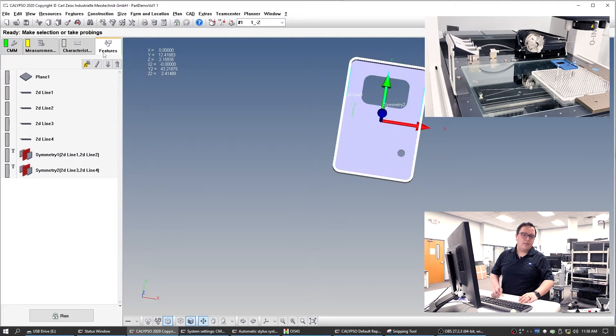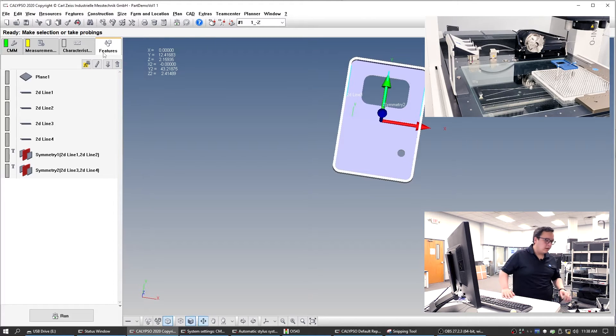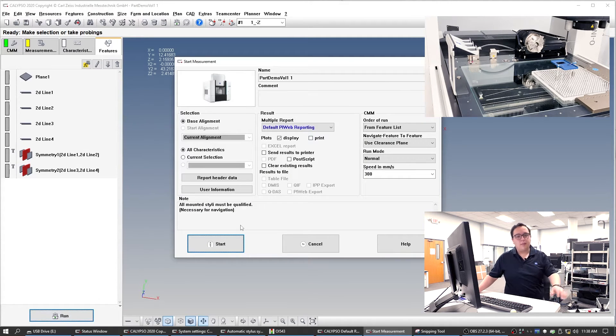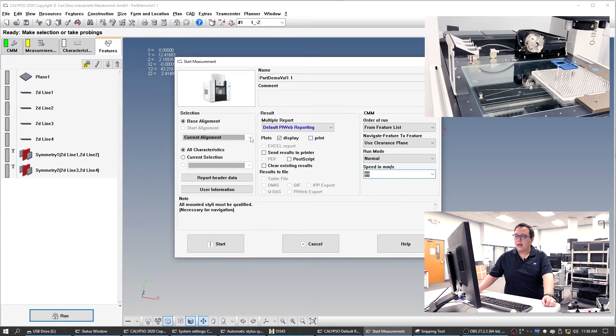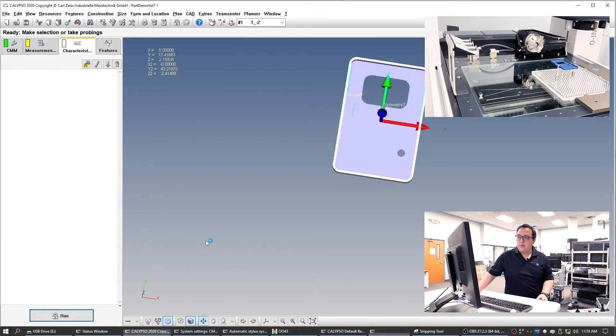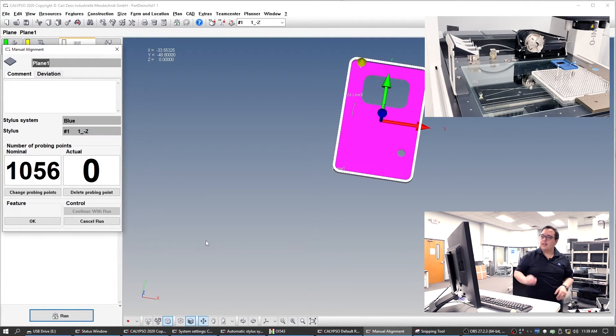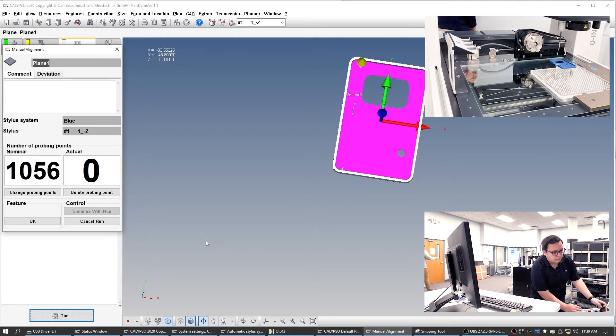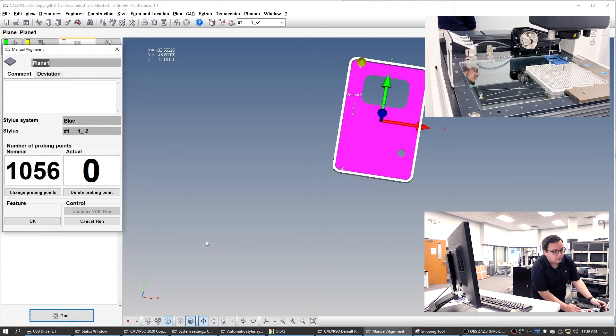Let's do a quick run to make sure that the CMM knows where the part is, and then we'll start adding things like the circle and the slot. We'll go to run — this also lets us run the initial program a little slower, which is always good to start. It keeps us from having any collisions. We'll clear the existing, we'll do a manual alignment here. It says all characteristics — we don't have any characteristics yet, but we will. So we can go ahead and start this alignment. Now it says it needs me to probe a thousand points — what we're going to do is probe about three or four. That will give it an idea of where the plane is.